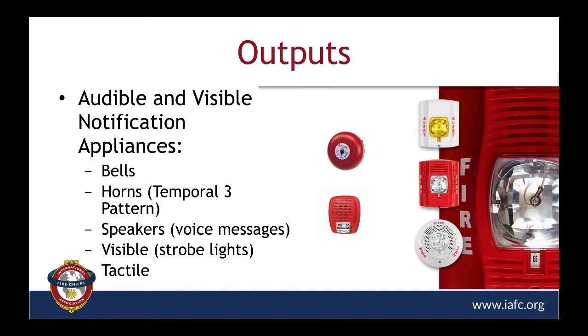And then, of course, visible lights, typically referred to as strobes, they alert people by the sense of sight, and they notify the building occupants. Their primary purpose is to notify building occupants who may be deaf or hard of hearing. So if they can't hear the voice message or the horn, these strobe lights alert people who are hard of hearing or deaf. And tactile: it's a notification appliance that alerts people by the sense of touch or vibration. A lot of times in hotel rooms, you could get people who are hard of hearing. They can request a bed shaker or some sort of vibrating device that will wake them up in the event of a fire.